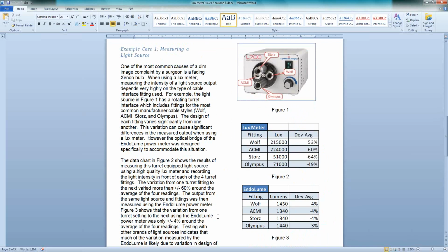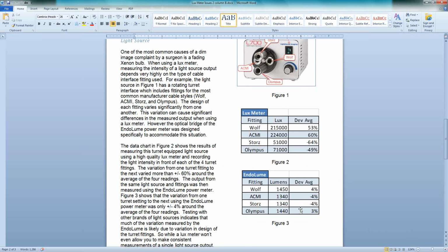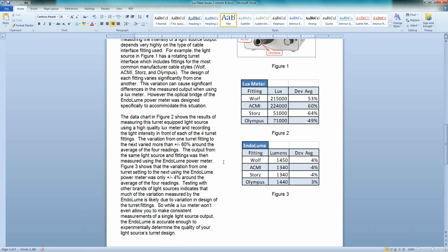So if I go back to a page before in this paper, we see that measuring just the same light source in the different turret settings, you could measure anywhere from 51,000 lux to 224,000 lux for the same light source in the same settings just by changing the turret setting. So that's 120% difference. Well, almost, actually that's from the average. It's actually a factor of 4 from the weakest to the strongest. If we do that same measurement with the EndoLume and all the different turret settings, we get a small variation of just a few percent. And experimentally, I've actually shown that this is variation in the turret. With other light sources that have a little better quality turret design, you actually get virtually no difference in the output, which is as it should be.